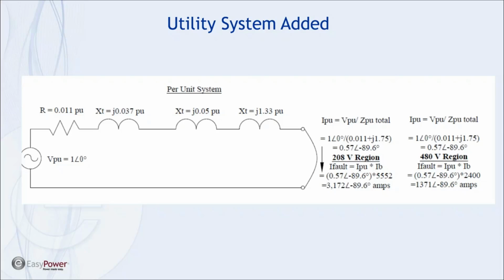The thing we have to be careful with, when fault currents are being reduced in some fashion, that's also increasing the trip time on breakers and fuses. And so sometimes it can have a positive impact on available flash, sometimes it can have a negative impact on available flash.